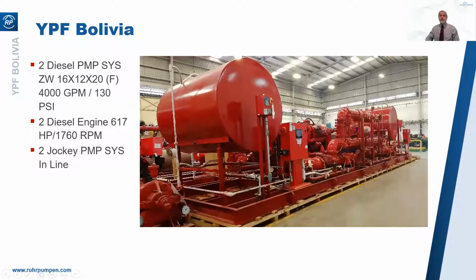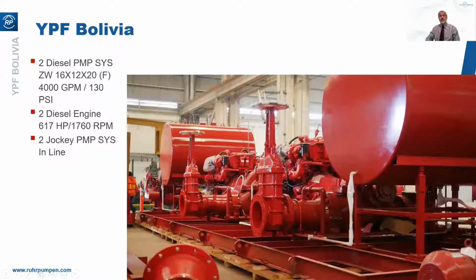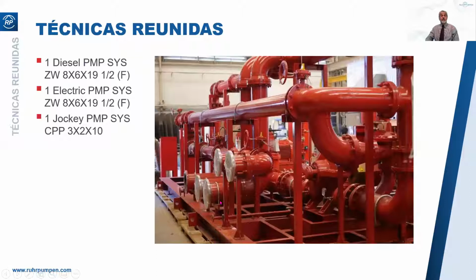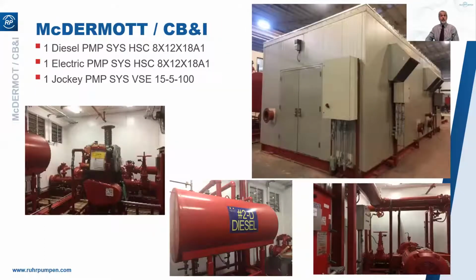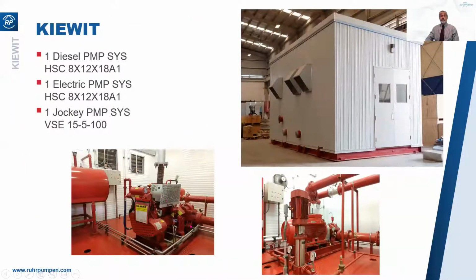This package has two diesel-driven pumps side by side in like a 69 configuration, you might say. See a day tank there, and the two engines side by side. Shame we haven't got a vertical view on this one. There are a 3-pump skid. And here, I think it's an H60 enclosure housing with 3 pumps in one. And there we get a view inside the housing.